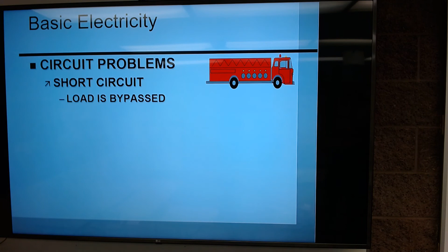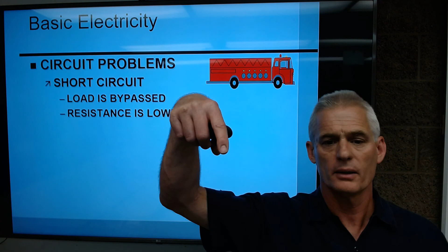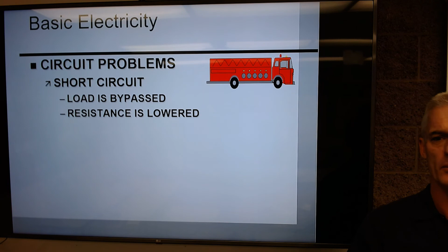We say the load is bypassed, like it says there in the PowerPoint. Consequently, resistance drops because the horn's probably not in the circuit anymore. So we've got the load bypassed, we have resistance lowered, and we have high current flow. And when we get high current flow, we're going to make heat, smoke, and fire. We're going to burn things.